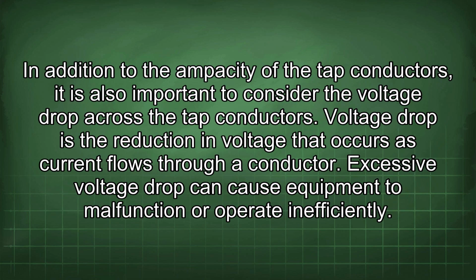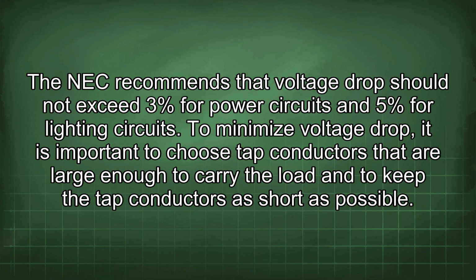In addition to the ampacity of the tap conductors, it is also important to consider the voltage drop across the tap conductors. Voltage drop is the reduction in voltage that occurs as current flows through a conductor. Excessive voltage drop can cause equipment to malfunction or operate inefficiently. The NEC recommends that voltage drop should not exceed 3% for power circuits and 5% for lighting circuits. To minimize voltage drop, it is important to choose tap conductors that are large enough to carry the load and to keep the tap conductors as short as possible.